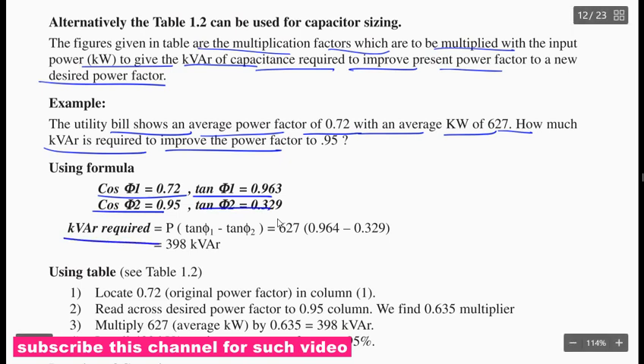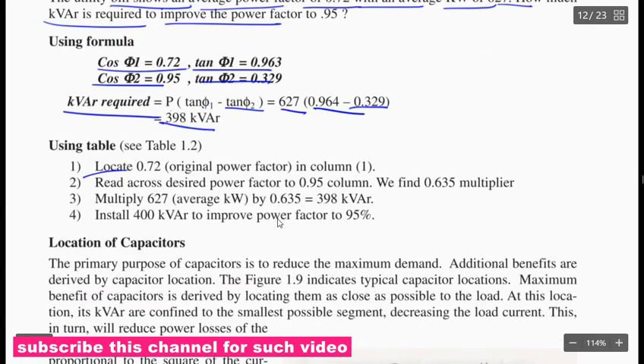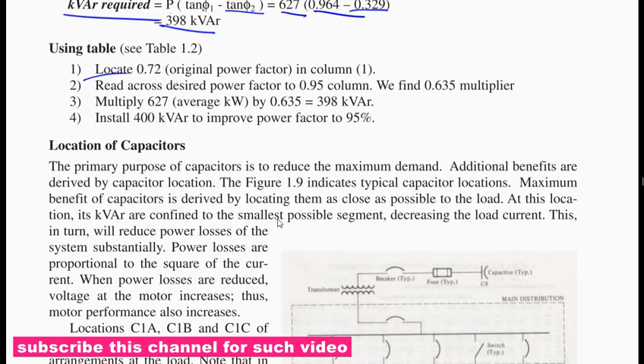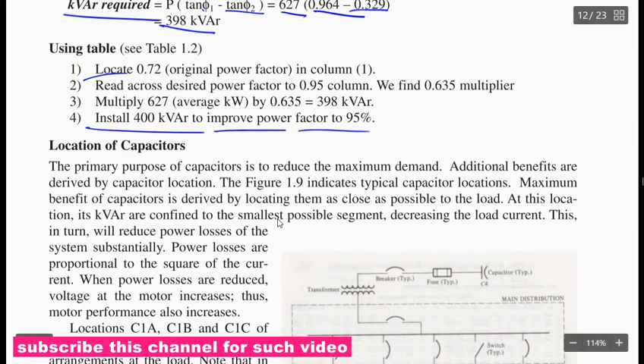Using the formula, kVAr required is P times (tan phi 1 minus tan phi 2), equal to 627 times (0.964 minus 0.329), that is 398 kVAr. So we can locate this according to the table, or we can apply this method. So install 400 kVAr to improve the power factor to 95%.